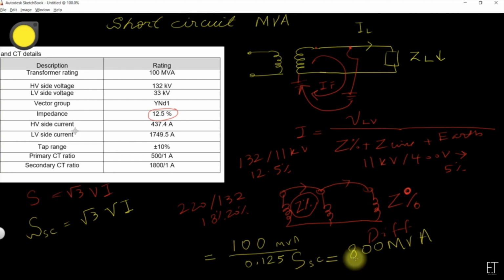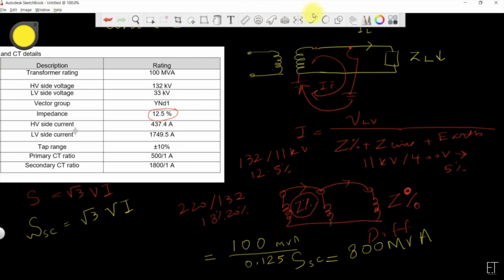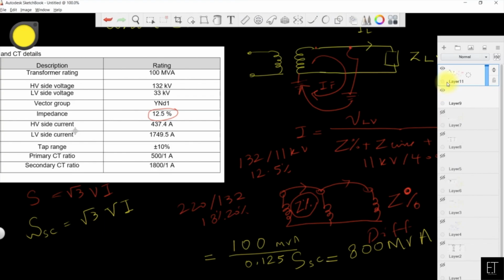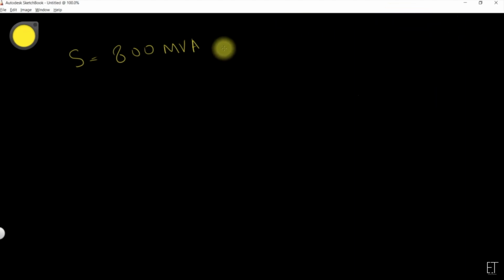MVA short circuit. So what does it mean? It simply means, now we have calculated S equal to 800 MVA, and this is the short circuit impedance of a transformer. This is a 132 kV by 33 kV transformer. If I want to calculate the short circuit level at the low voltage side, I have to use the same formula, which is equal to √3 V into I.